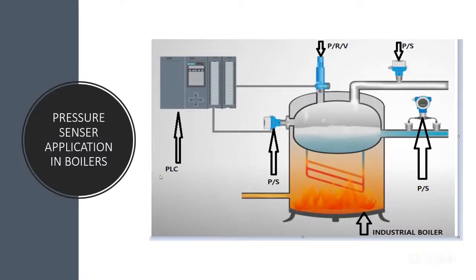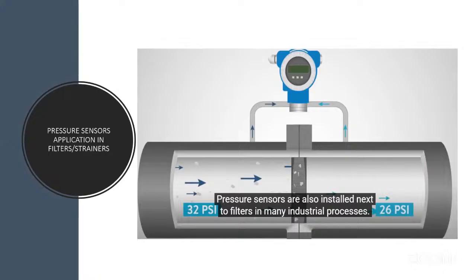And we can go over to the next slide. Here, the differential pressure measurement. Here, pressure sensors are also installed with filters in order to check in different forms. For example, like this picture shown here, it's a direct flow of liquid, and you can see pressure sensors in this case installed on either side of a strainer or a filter. We check the incoming pressure on one side, and the outgoing pressure on the other side, and then we compare the pressure. When there is a very high difference in the pressure, the value is given to the PLC, the programmable logic controller, via the card, and a little programming is already done inside.